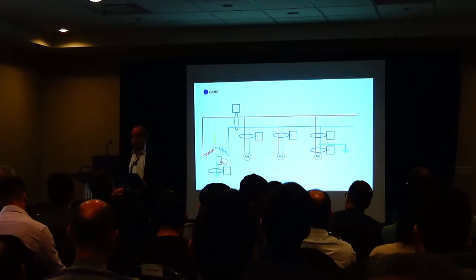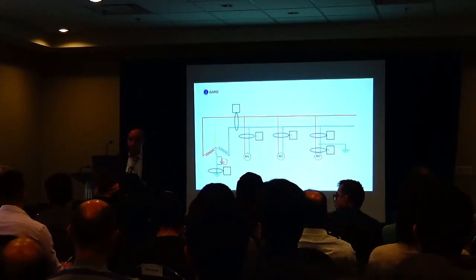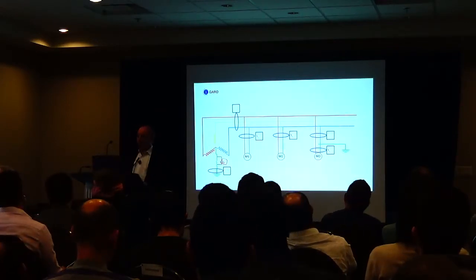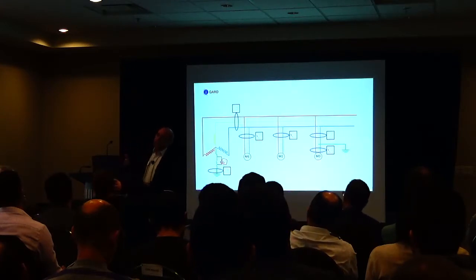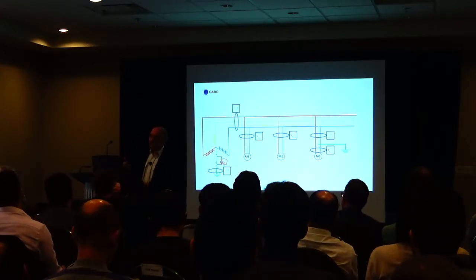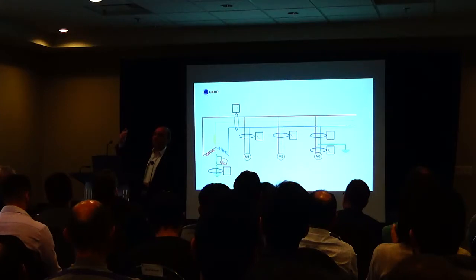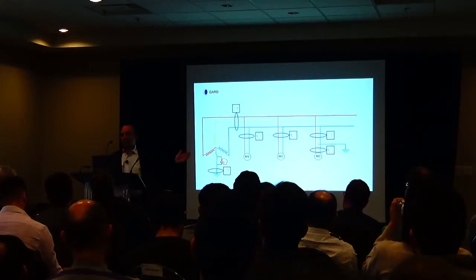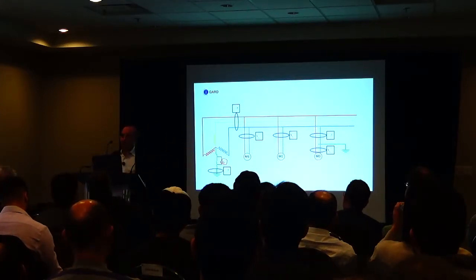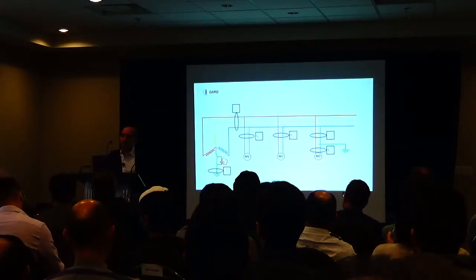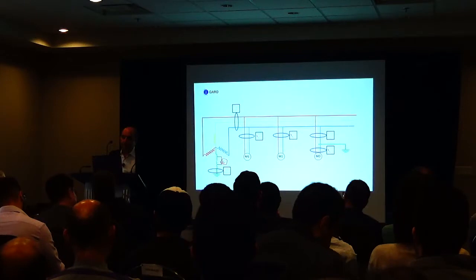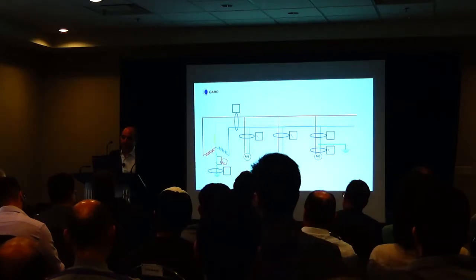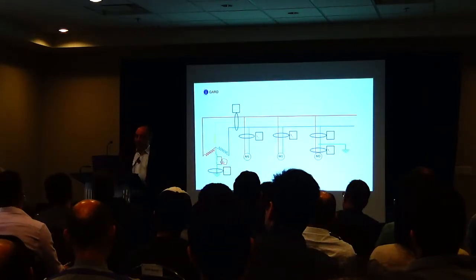You still got to put in those transformers with that. Yes, you are. And now when you calculate incident energy, you have much less incident energy because you have a 112 kVA transformer as opposed to a 2 MVA transformer feeding those ballasts. So in your cost benefit though, you're still going to save on the whole wire part of it. That's right. You've got to create these other.